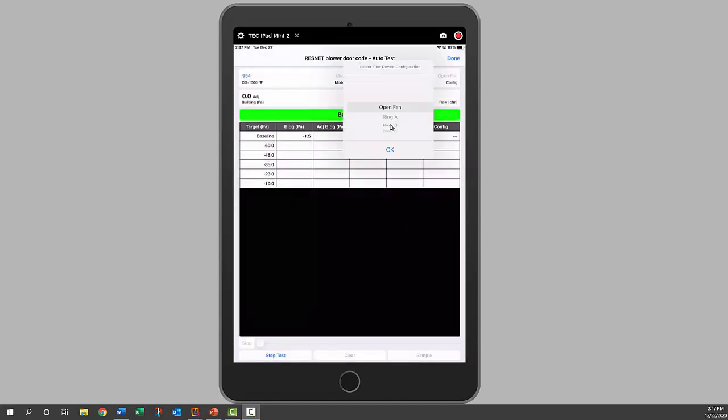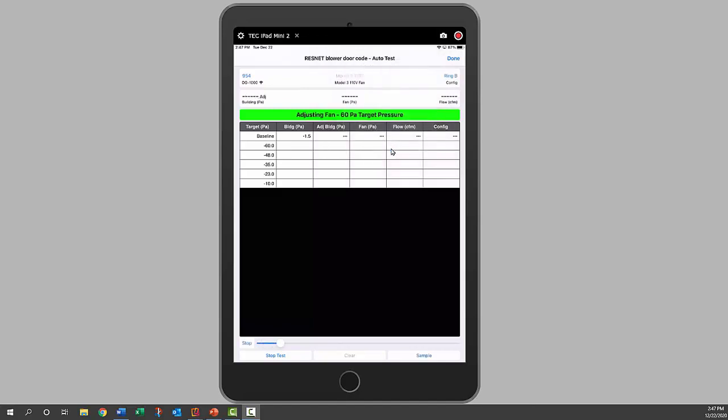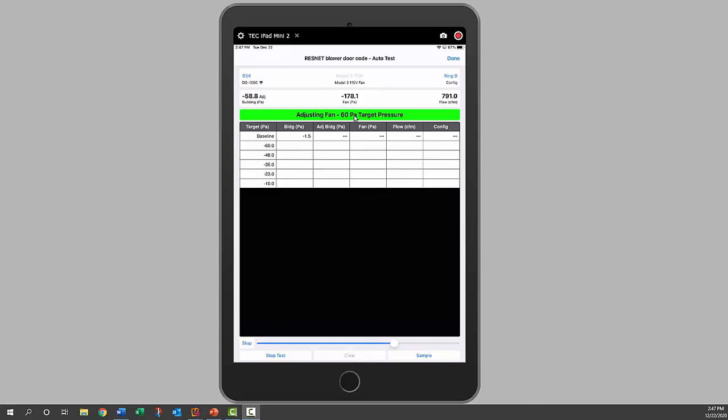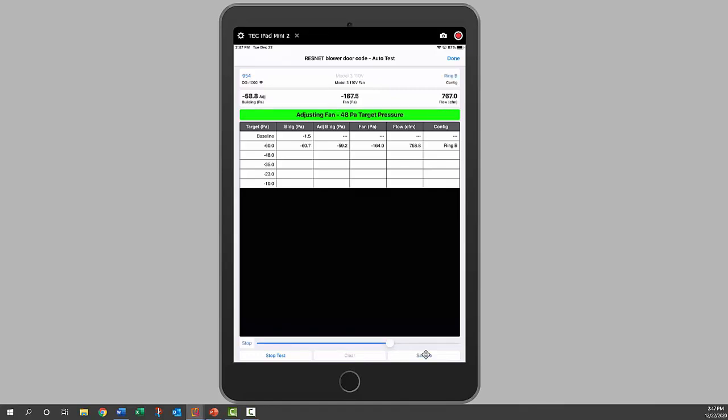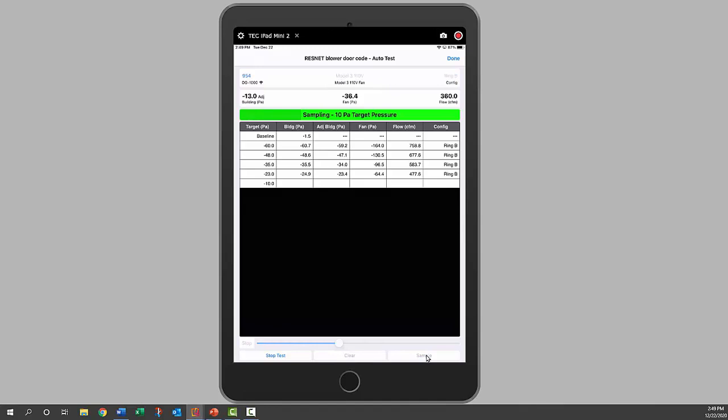We're going to go to ring B and click okay. We can see it's starting up, it's ramping up. We can see our pressures. Our first target pressure is 60 pascals, so it's searching for 60, it's adjusting the fan to 60 pascals and sampling data. Now it'll start going towards 48. Now it's sampling the data for our 10 pascal pressure.